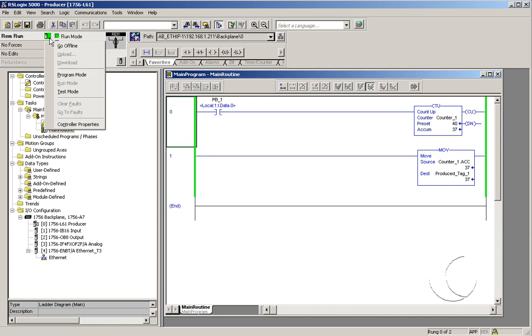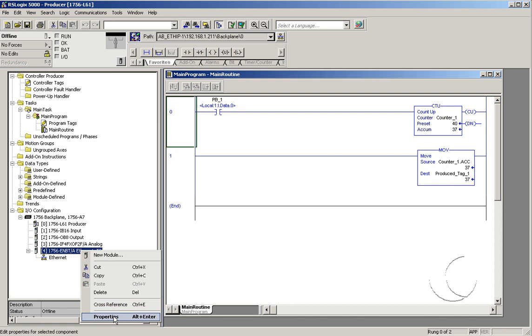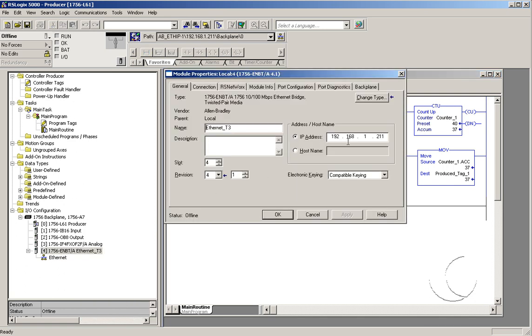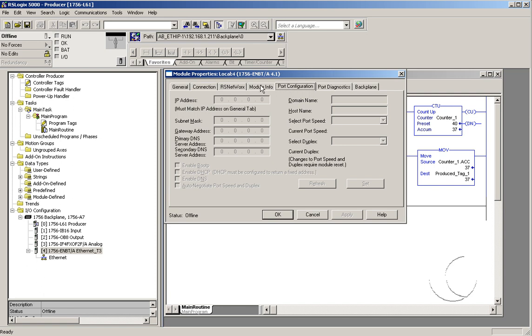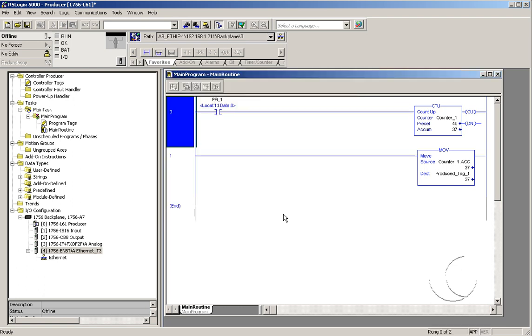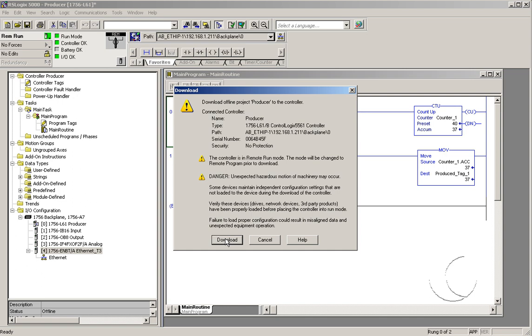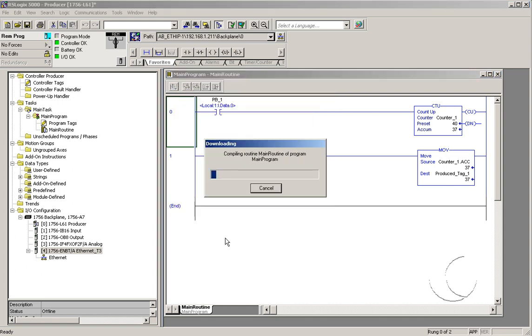So first of all, I'm going to go offline. Then I'm going to right-click on the IO configuration for the 1756 Ethernet card and click on Properties. Now here, depending on the version of RSLogix you're running — this is version 17 — this screen may look different, but there are two places where the IP address is showing. One is in the General tab, and when you're online, you will also see it in the Port Configuration. While you're offline, you want to change the IP address. So I'm going to change the 211 to 222. Do not change the front part — this designates the network portion. Click Apply, click OK, then download this change. This will only change the General Properties, not yet the IP address displayed on the Ethernet IP card.